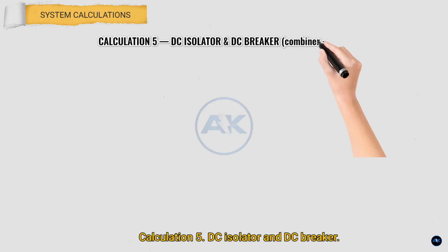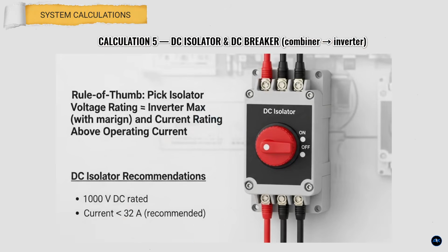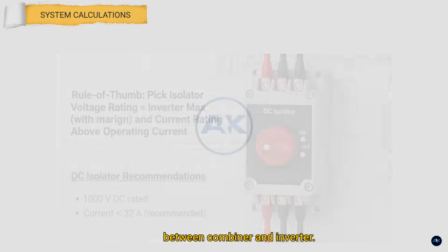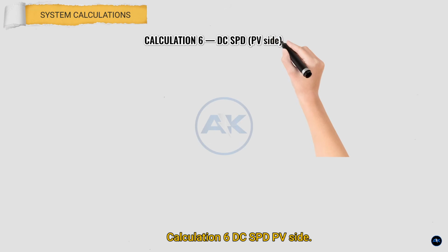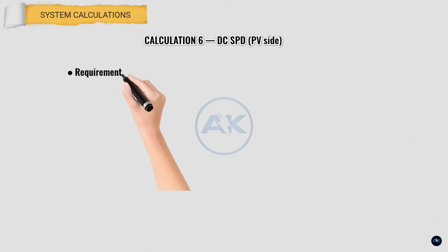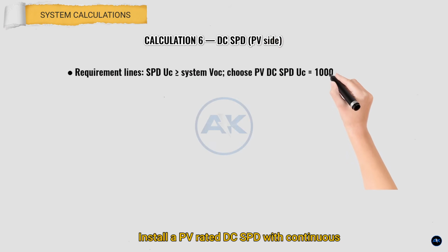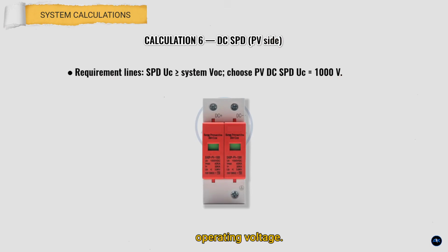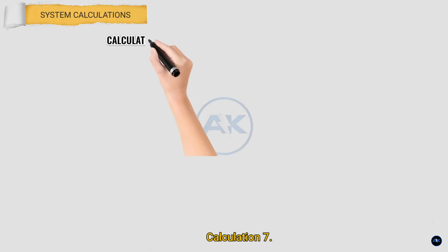Calculation 5. DC isolator and DC breaker. Combiner to inverter. Use a 1000 volt DC rated isolator, industry norm for extra margin, and a 32 amp DC breaker between combiner and inverter. Calculation 6. DC SPD, PV side. Install a PV-rated DC SPD with continuous operating voltage, UC, greater than the PV VOC. In practice, use a 1000-volt DC SPD in the combiner box for reliable protection. Calculation 7.